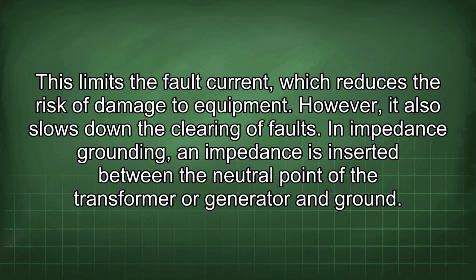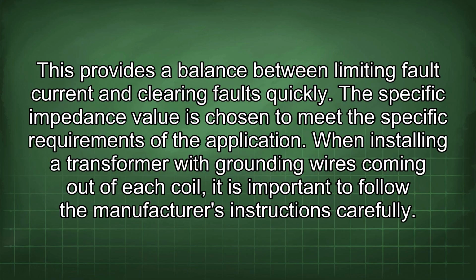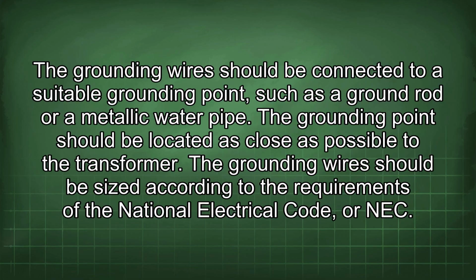In impedance grounding, an impedance is inserted between the neutral point of the transformer or generator and ground. This provides a balance between limiting fault current and clearing faults quickly. The specific impedance value is chosen to meet the specific requirements of the application. When installing a transformer with grounding wires coming out of each coil, it is important to follow the manufacturer's instructions carefully. The grounding wire should be connected to a suitable grounding point, such as a ground rod or a metallic water pipe. The grounding point should be located as close as possible to the transformer.